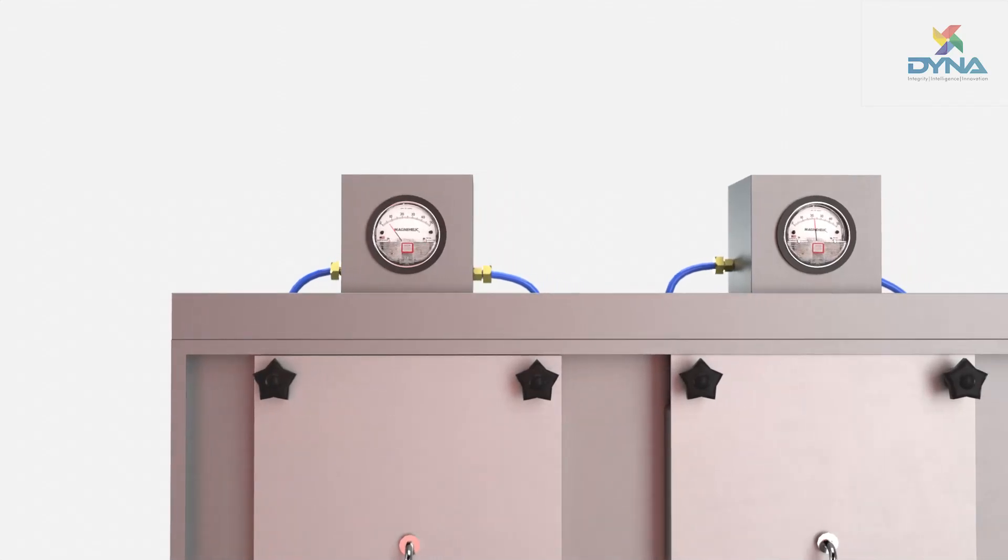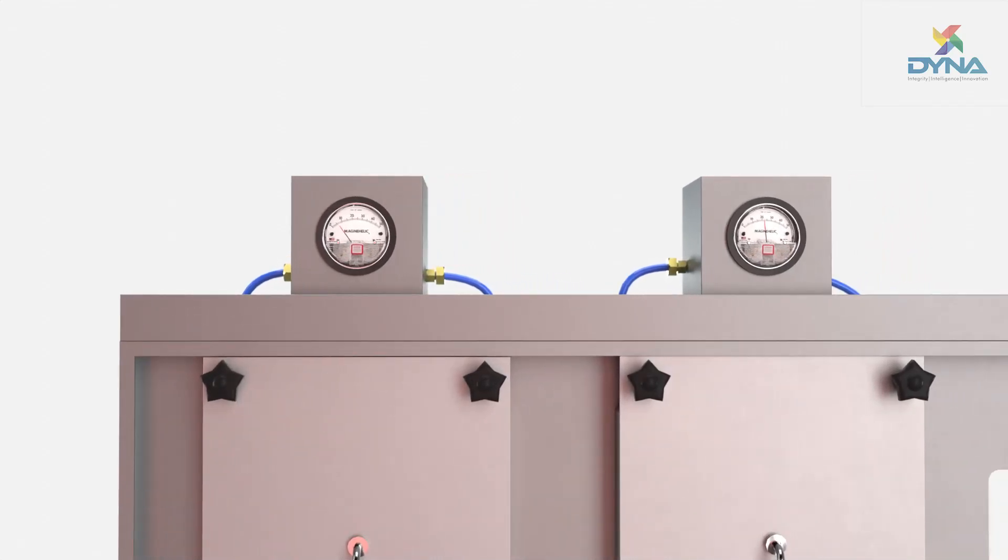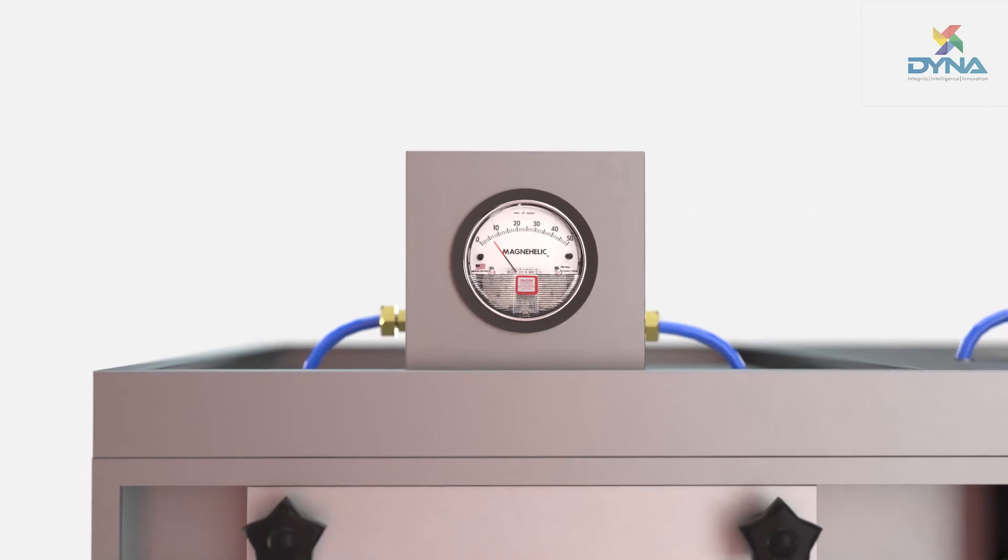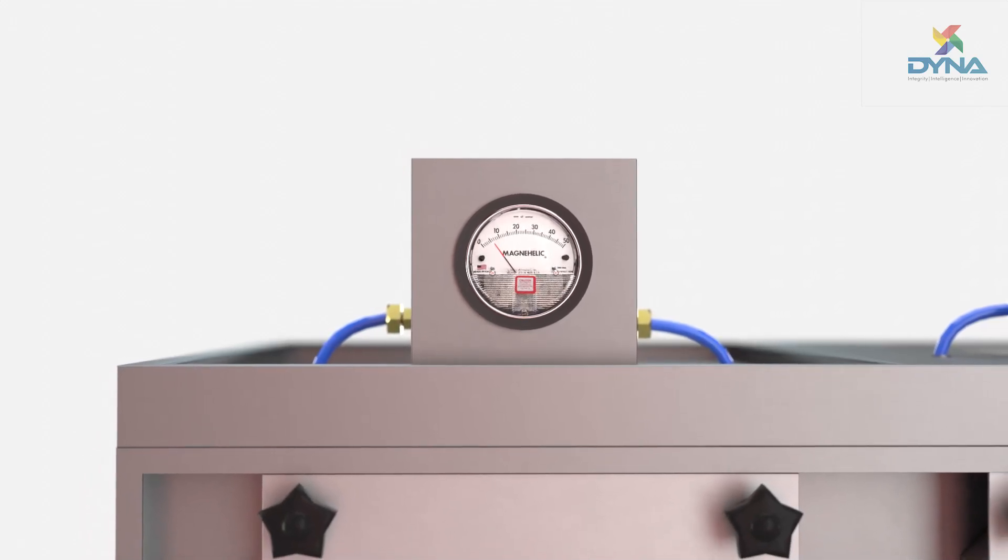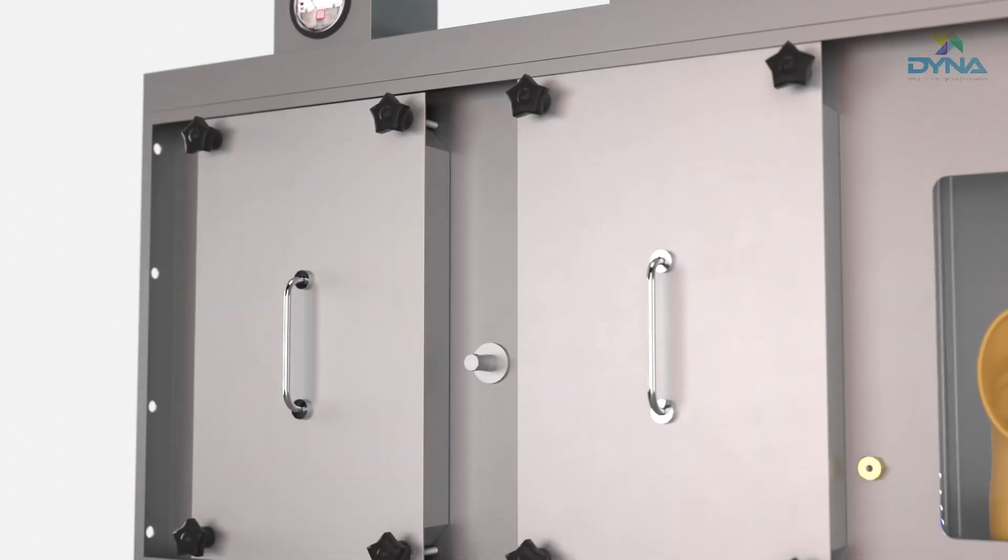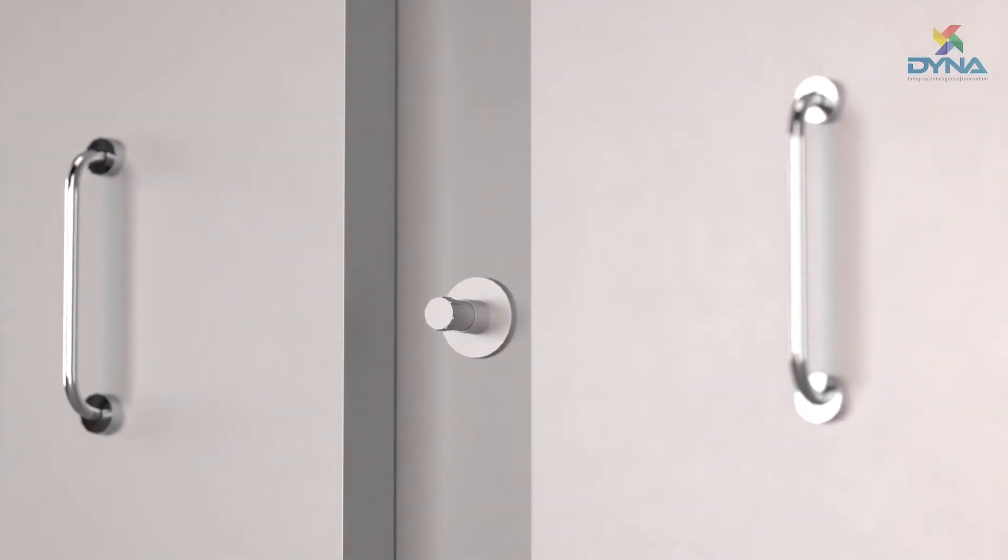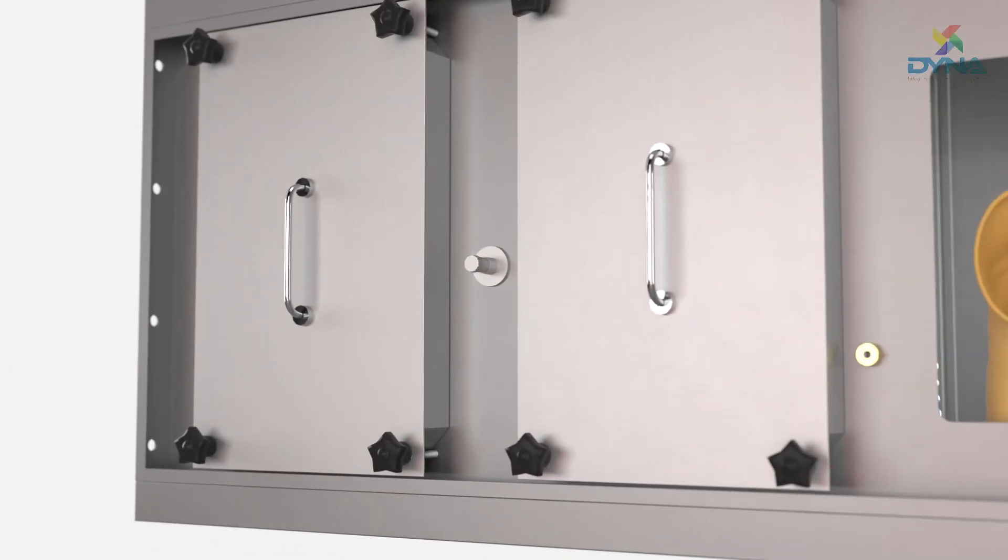Pressure gauges are installed on the BIBO system that monitor the pressure differential to indicate the changeover. An aerosol injection port is provided before the HEPA filter to count the upstream concentration.